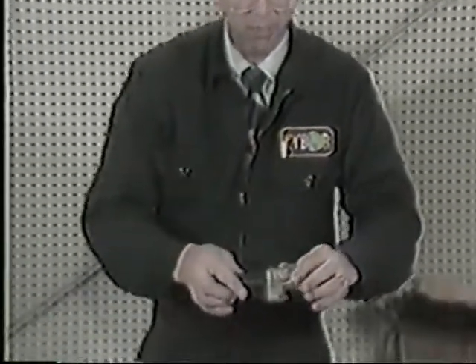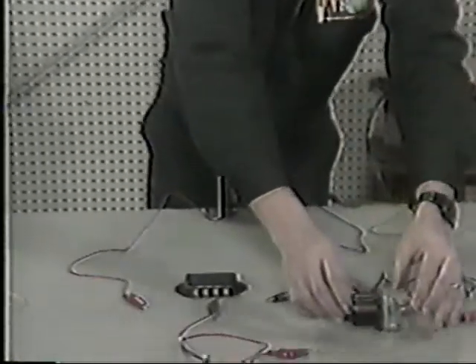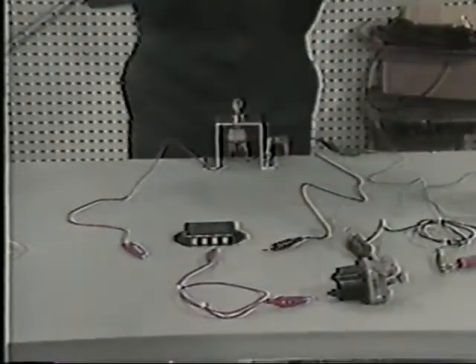Troubleshooting Area 8, module bench testing. This is similar to what we did in alarm-only systems, but this time we need an additional tool, a fuel solenoid to use as a load. Without a load, a module could test good when in fact it has a problem. Let's begin by testing the 9032 system automatic override.